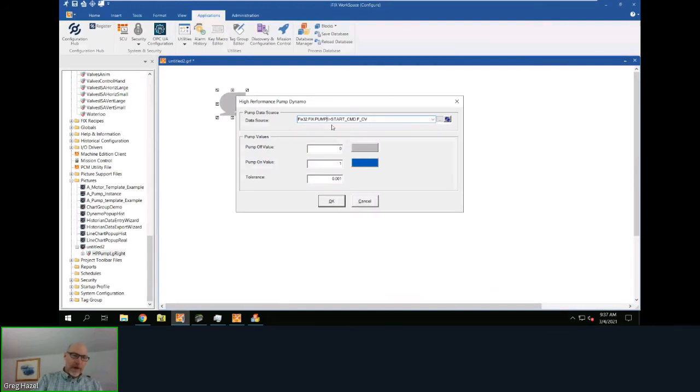Here, I'm going to use my placeholder again. I'm going to use my @ symbol and put in my substitution again. This is my pump number. And here we're using the symbol function, kind of like tag groups in iFIX. We're going to use that symbol number to substitute that particular attribute of the tag. Okay, so as I click on here, it's going to do a substitution of that tag. All right, we got that pump and the command button.